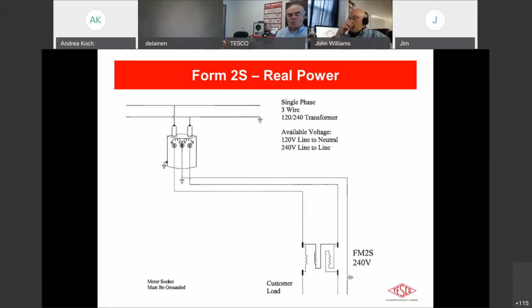The next one we have, of course, I don't think we need a whole lot of examples here, but this is our standard 2S meter, our typical residential meter. We have a 3-wire pole transformer, 3-wire source into the house, non-Blondel compliant, and you have your voltage across, your current through the 2 legs going into the circuit breaker panels in the homes, and pretty simple application. We all know mostly about this one.